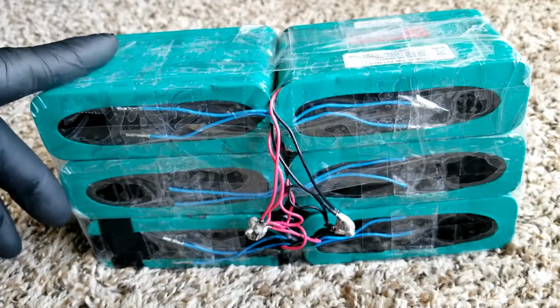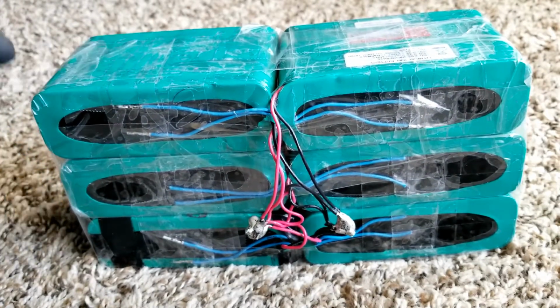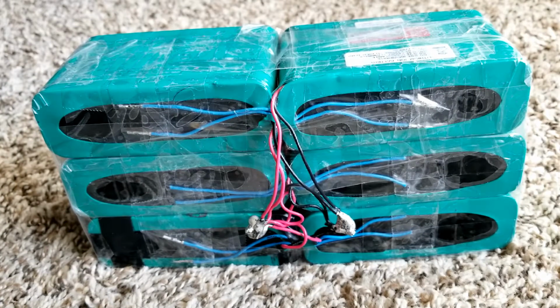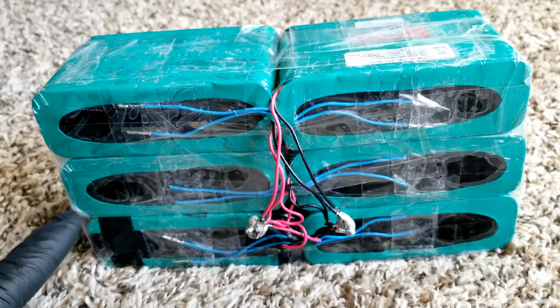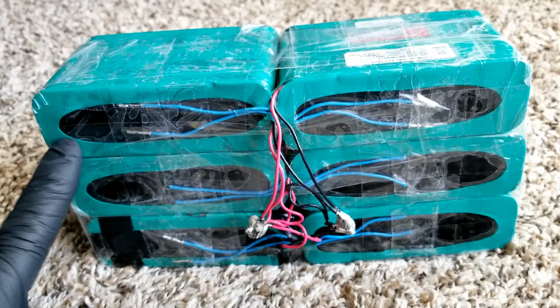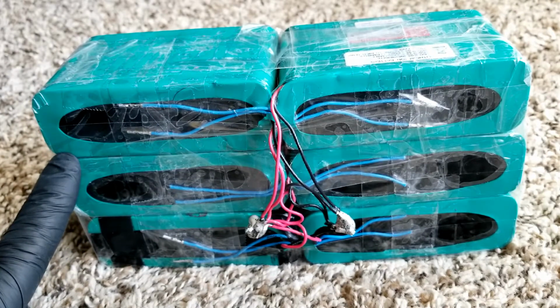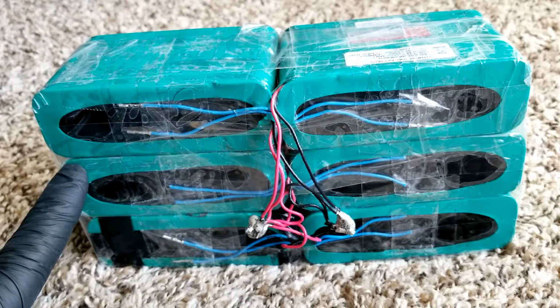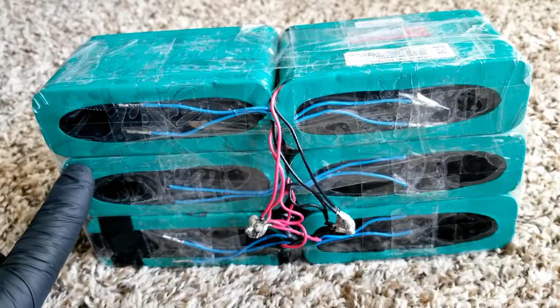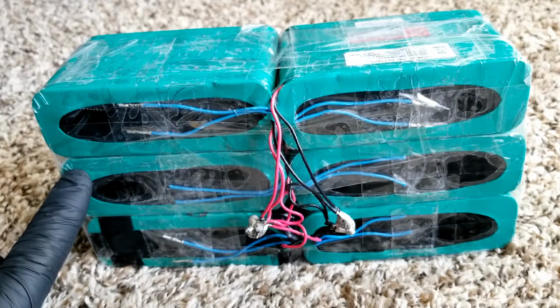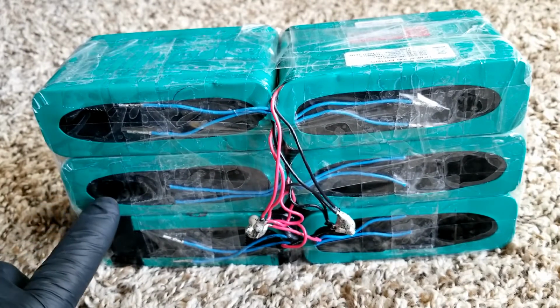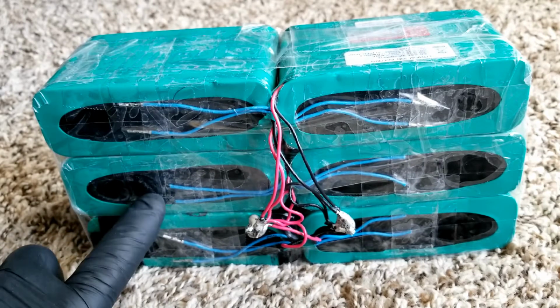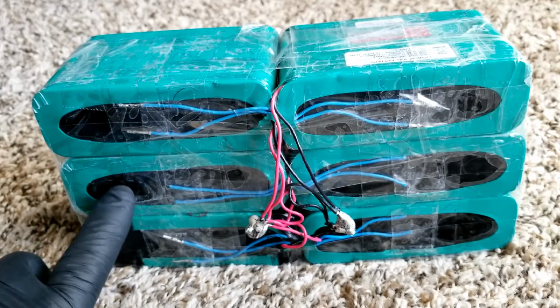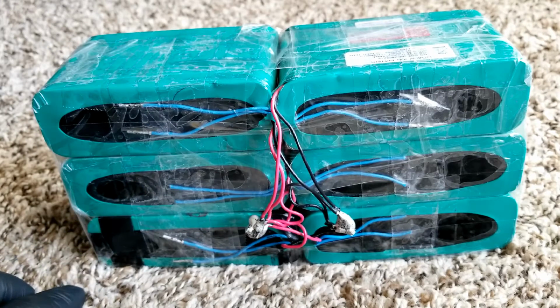So go back to this. The top charge, top balancing is 16.8, then the BMS will disconnect. And the bottom balance is 11, or the lowest discharge disconnect. Fully discharged, this battery is at 11.2 volts, and the BMS will shut itself down so it doesn't destroy the batteries.